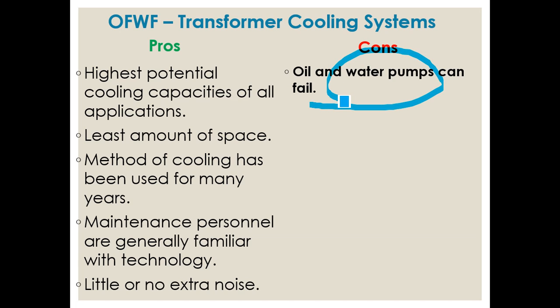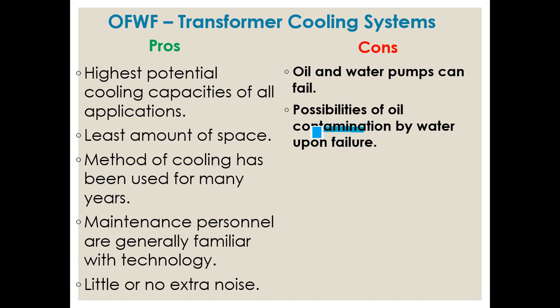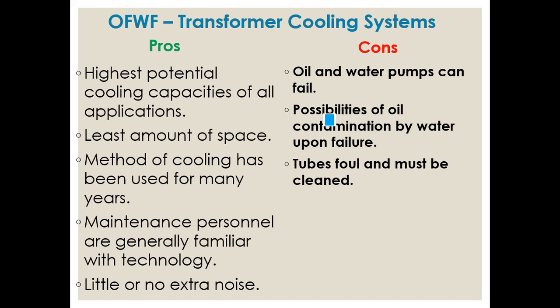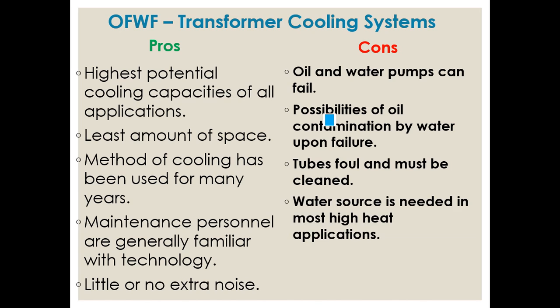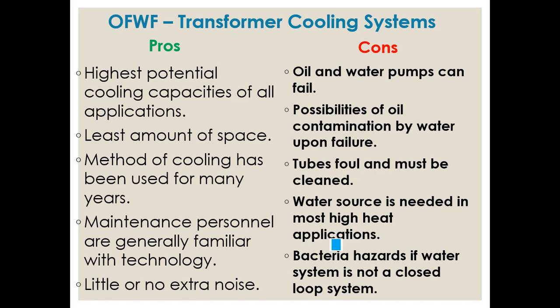In OFWF, the oil pump or water pump can fail, and if it fails the cooling capacity will suddenly reduce. Oil contamination can also occur in the heat exchanger - practically the oil and water should not mix, but there is a chance of contamination. Tubes can become fouled and must be cleaned. A water source is needed, and the water itself can become hot at the output. Bacteria hazards will be there if it is not a closed loop system.